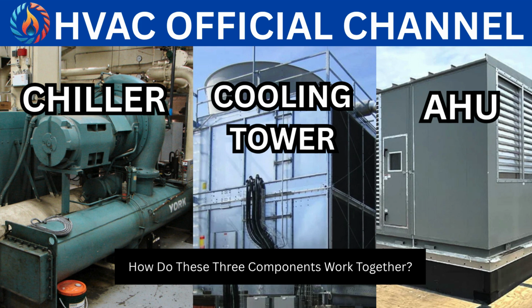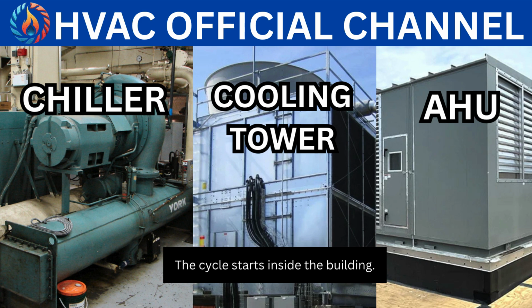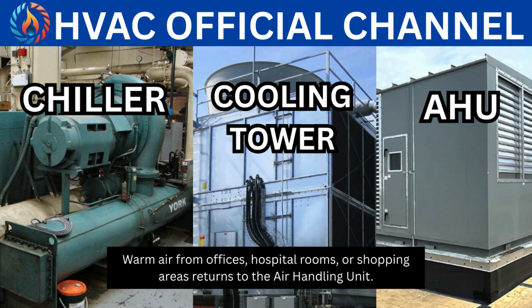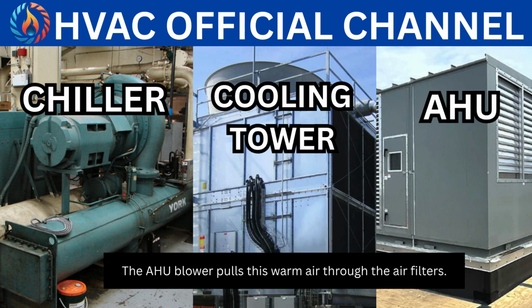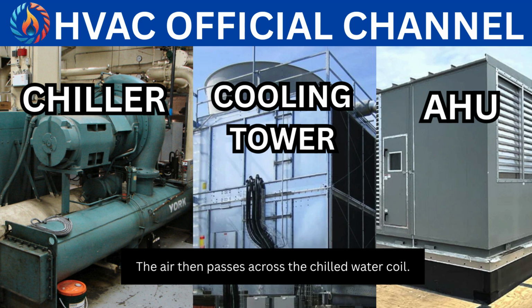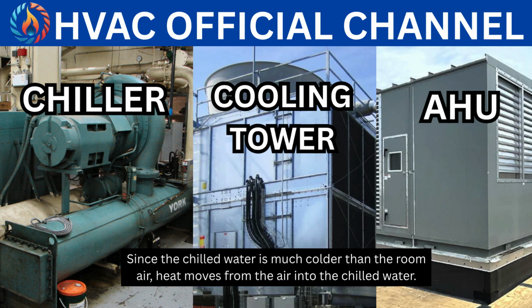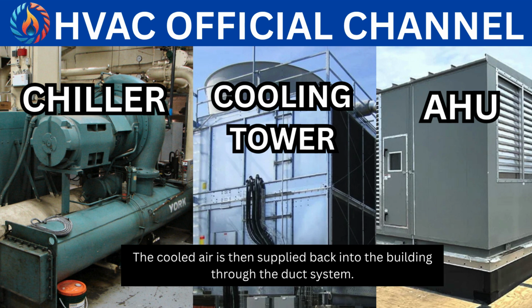How do these three components work together? Now let's understand the complete cooling process. The cycle starts inside the building. Warm air from offices, hospital rooms or shopping areas returns to the air handling unit. The AHU blower pulls this warm air through the air filters. The air then passes across the chilled water coil. Since the chilled water is much colder than the room air, heat moves from the air into the chilled water. The cooled air is then supplied back into the building through the duct system.